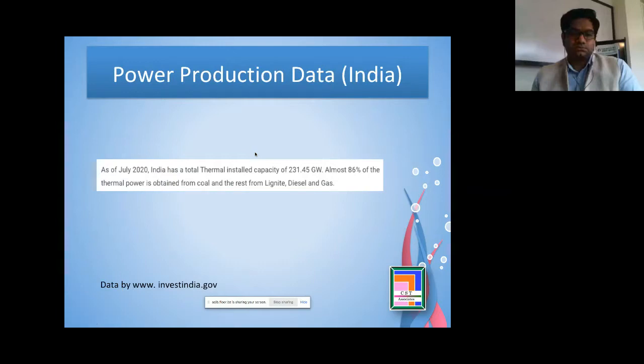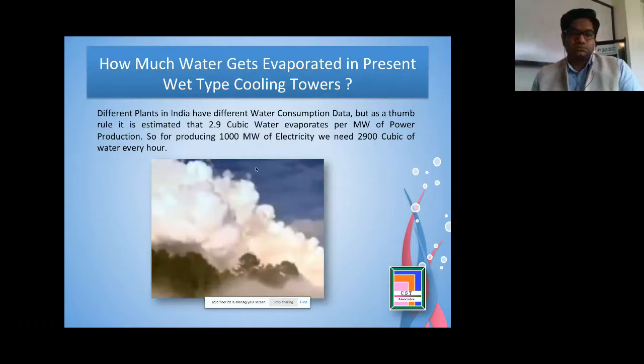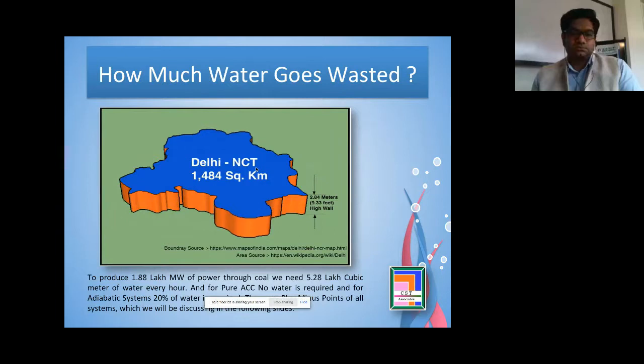So to understand how much water is being used in Indian industry, as per July 2020, India has a total thermal installation capacity of 231.45 gigawatts. Almost 86% of thermal power is obtained from coal and the rest from lignite, diesel, and gas. Different plants in India have different water consumption data, but as a thumb rule, it is estimated that 2.9 cubic meter of water evaporates per megawatt. So for the production of 1000 megawatt, we need 2,900 cubic meter of water every hour, which is a lot and huge.